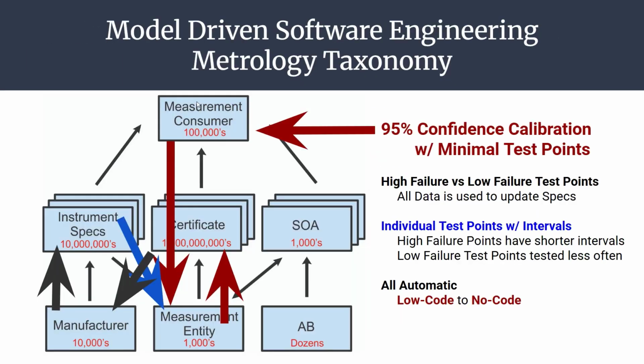So another one that's really out there is going to be this 95% confidence minimal tests. So now imagine that you got this big population of data, and you as a measurer, you as a customer, you want to save money on calibration, but the calibration lab is still going to charge you because it's labor. Imagine you could look at all of your high failure data points, your medium failure data points, and low failure data points. And you could statistically pick the data points that you want to have calibrated on your devices based on how you use it and where that make model fails. And you would have the statistical data behind that, you could get a 95% confident calibration with a minimum set of data points that you need to check to make that happen. These are all things you could do with getting metrology into a big data paradigm.